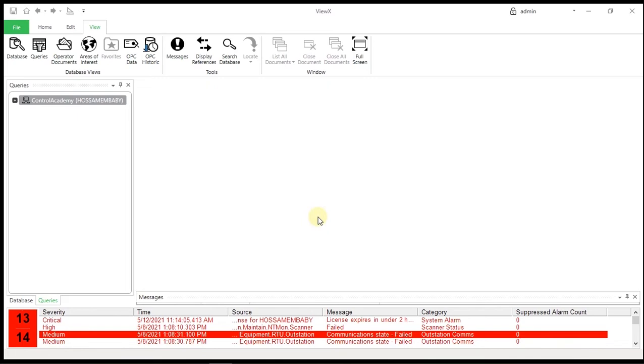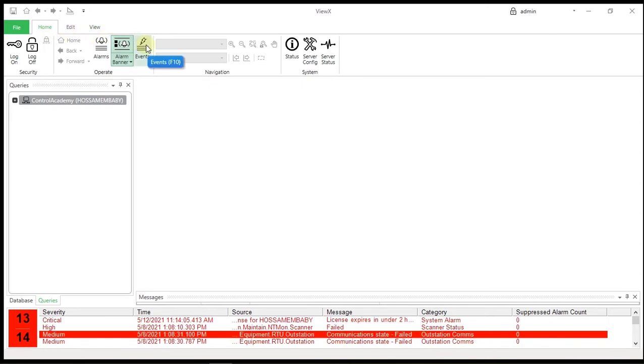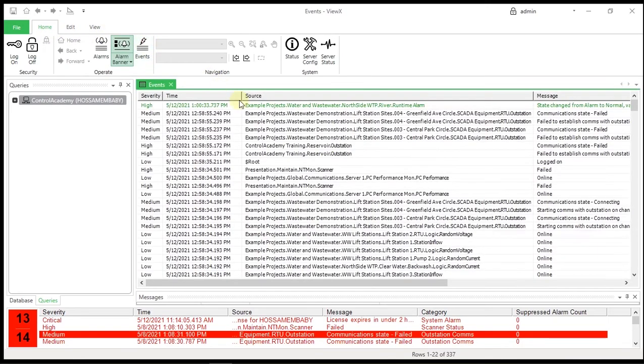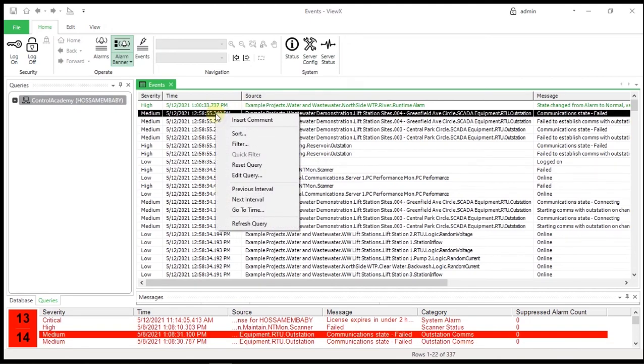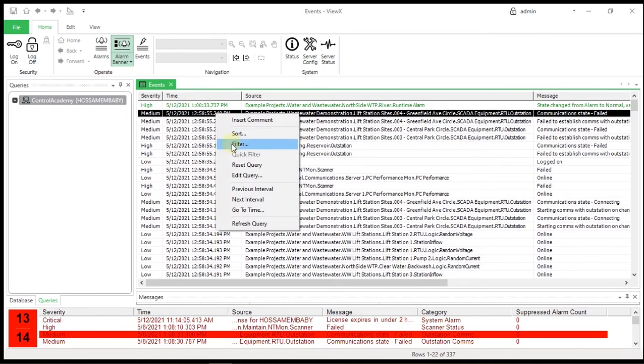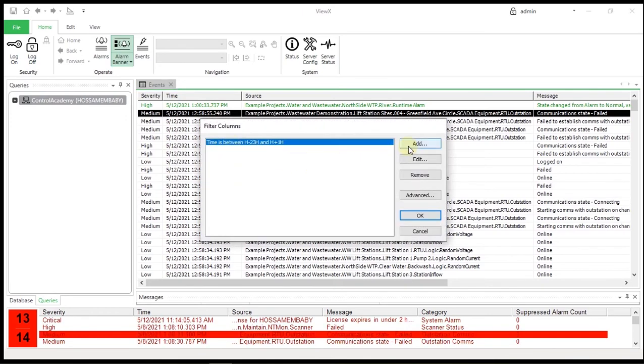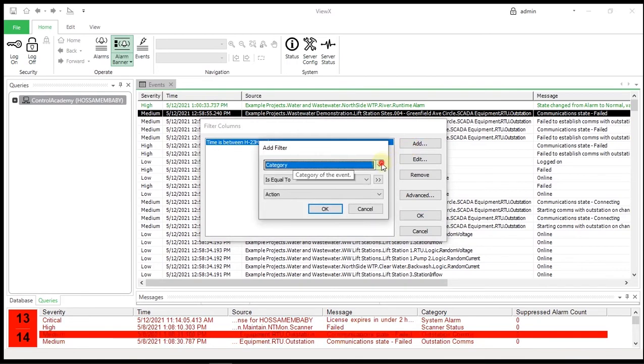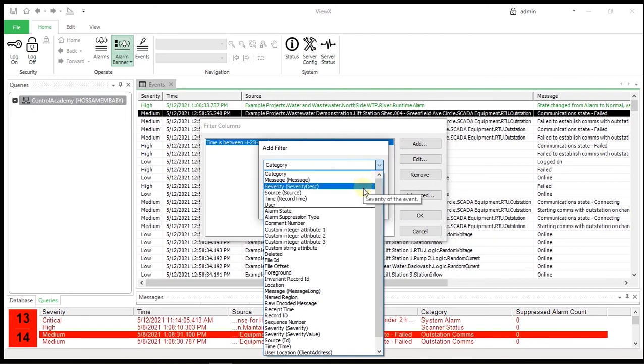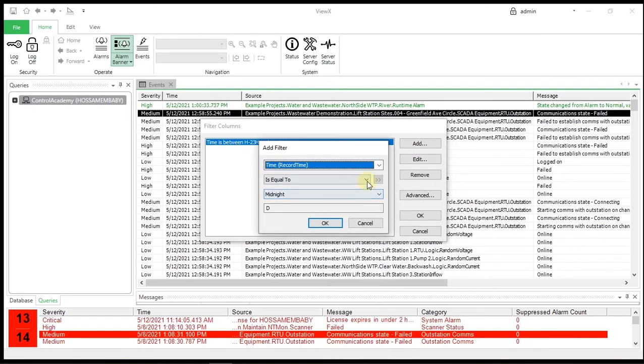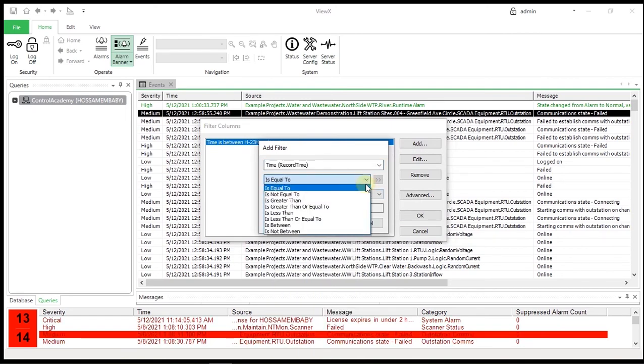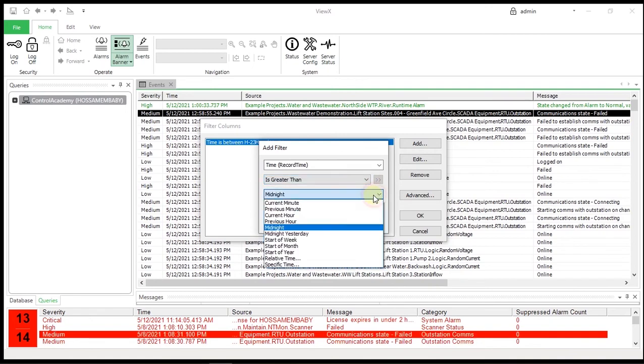To display the event list, click the events symbol on the home ribbon. Right-click the list and then select filter from the menu, alternatively press F7. Click add and then configure the settings. As a category, select time, then select is greater than, and select the current hour.